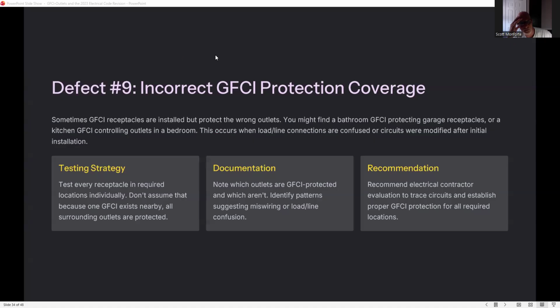Defect 9, incorrect GFCI protection coverage. Sometimes GFCI receptacles are installed but protect the wrong outlets. You might find a bathroom GFCI protecting garage receptacles or a kitchen GFCI controlling outlets in a bedroom. This occurs when line and load connections are confused or circuits were modified after initial installation.